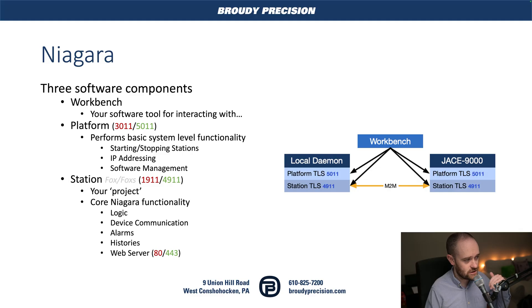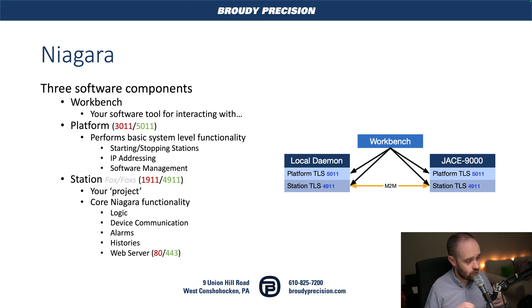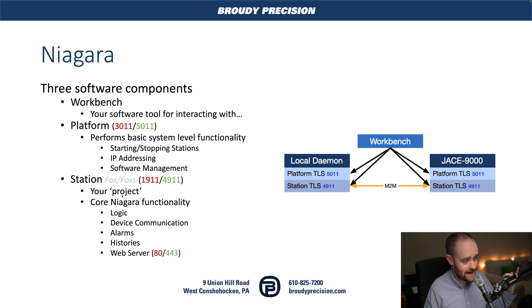You can see the ports listed here. Red indicates the unencrypted port — typically you won't be using that unless you're logging into a legacy station using an older version. All of our server connections default to TLS encrypted, using port 5011 for the platform. The next piece is the station — this is like our project, the core functionality in Niagara. It's where logic happens, device communication, alarms, histories, and graphics. The station connects via port 4911 on the TLS side, and the legacy unencrypted port was 1911.